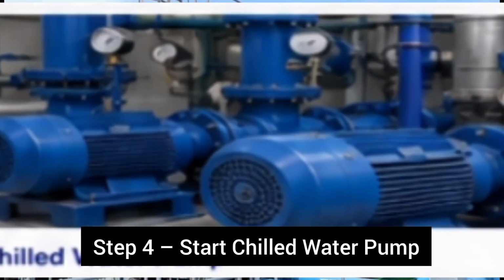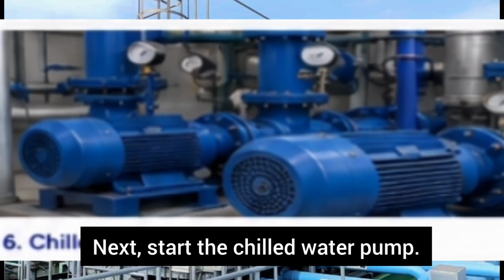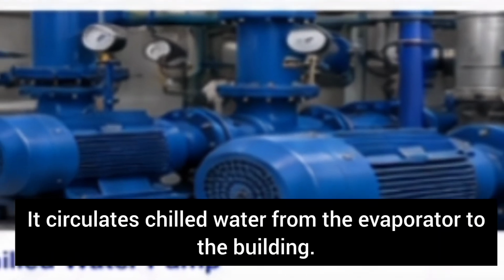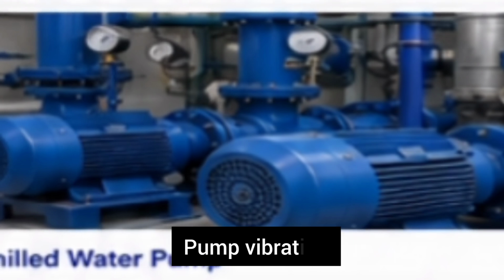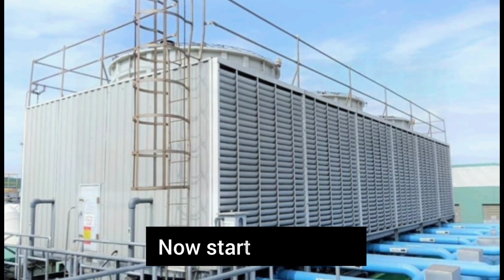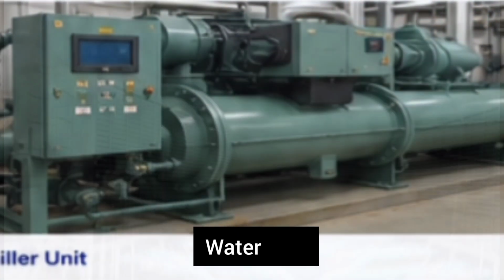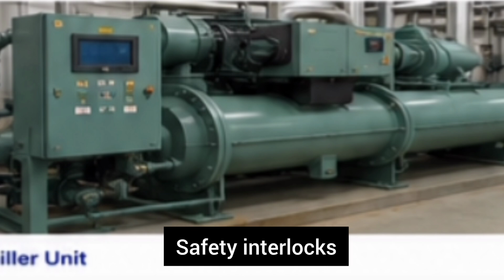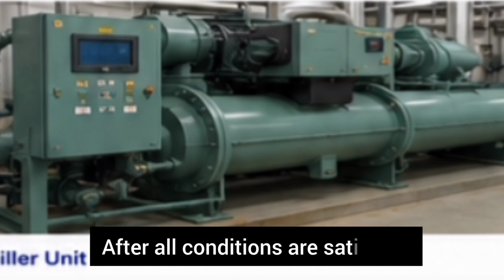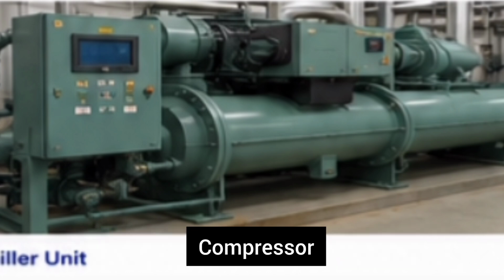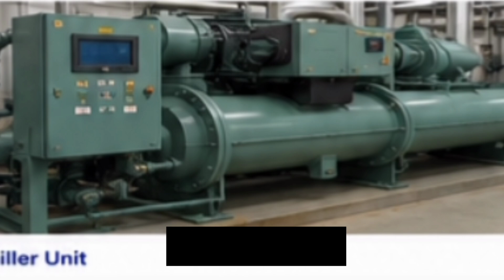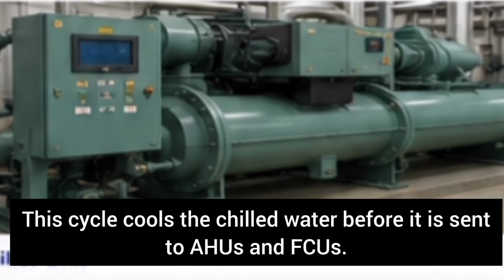Step 4. Start chilled water pump. Next, start the chilled water pump. It circulates chilled water from the evaporator to the building. Check differential pressure, flow rate, pump vibration, motor temperature. Step 5. Start the chiller. Now start the chiller. Most modern chillers first verify water flow, pressure, temperature, safety interlocks. After all conditions are satisfied, the compressor starts automatically. The refrigeration cycle begins. Compressor, condenser, expansion valve, evaporator. This cycle cools the chilled water before it is sent to AHUs and FCUs.